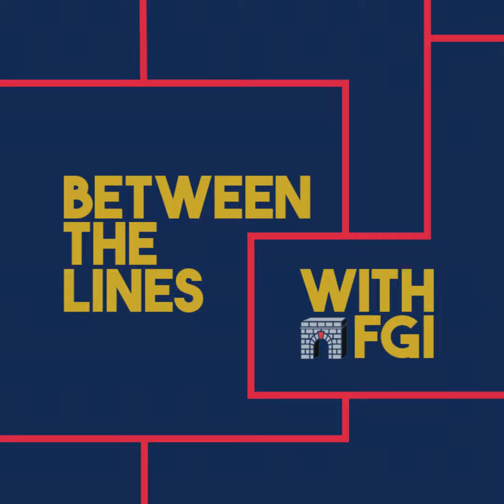And that's what I was looking to see, what the guidelines are for. Does ASHRAE 170 follow along with this? I don't believe that ASHRAE really touches on the specifics of cryogen venting. I think that's FGI that defines the design criteria for that. So we have a little bit of appendix in the 2022 guidelines, and the 2026 is going to show up in the handbook, that says that superconducting MRI systems that use trivial amounts of cryogen don't require quench pipes.